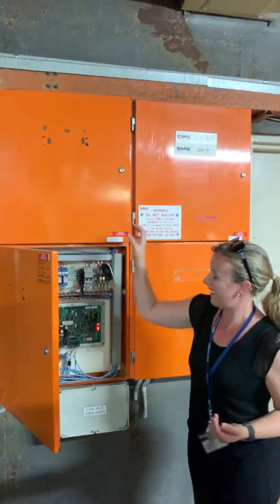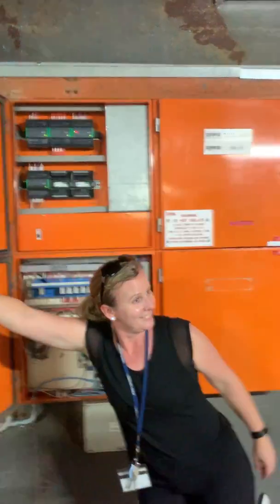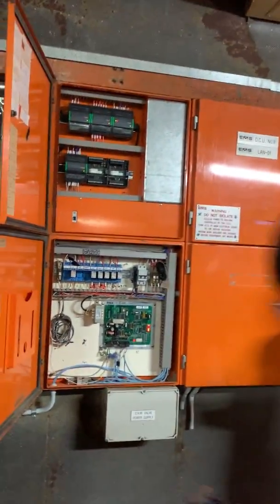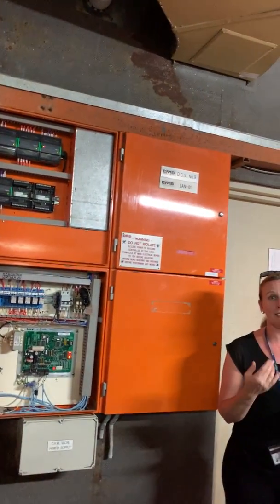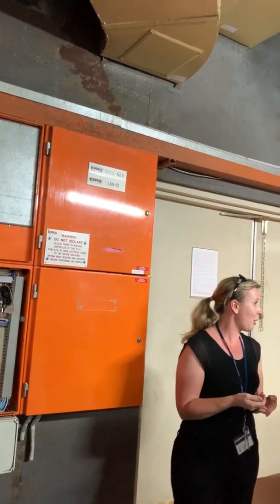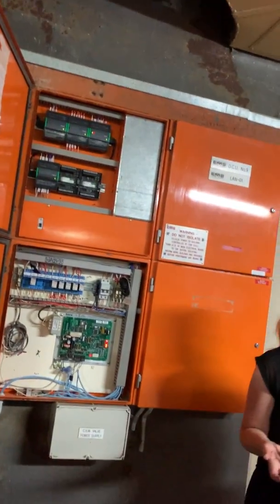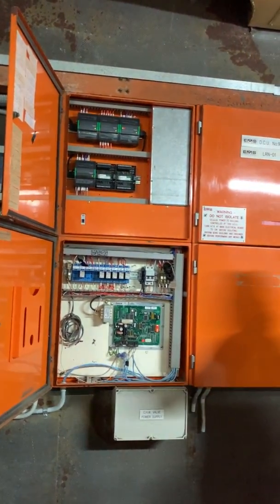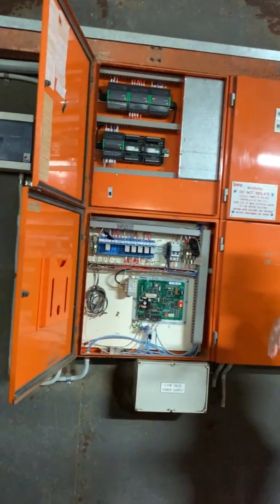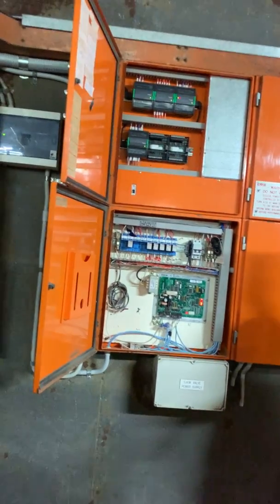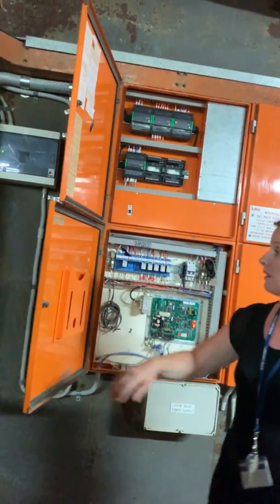This is part of the control system for the HVAC. So, you know, it's just like kind of computer bits, really. If you think about how the HVAC system needs to work, it's all automated. No one's turning it on. So the programs are in, what times it will operate, what temperatures it will operate at. The thermostats located within each of the zones are measuring the temperature, feeding that back into the control system, which then decides where chilled water needs to be sent, which chiller needs to be turned on. So all of the mechanical plant rooms that you see will have units like this, and they're part of that control system, building management that we have.